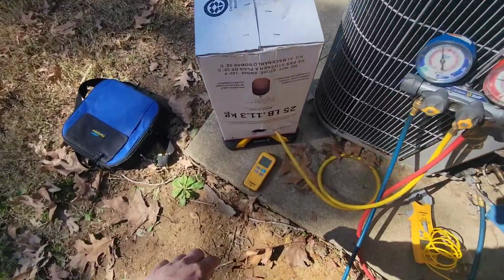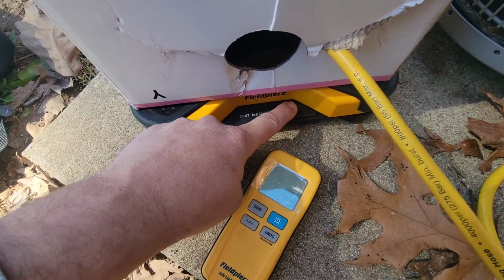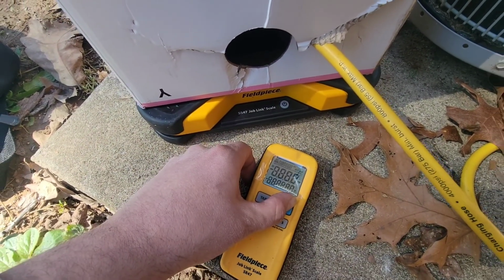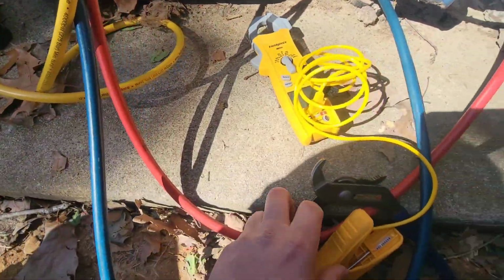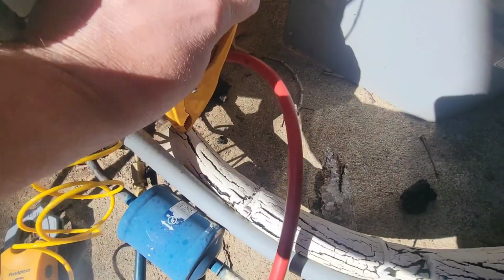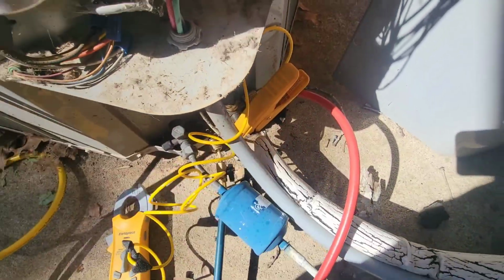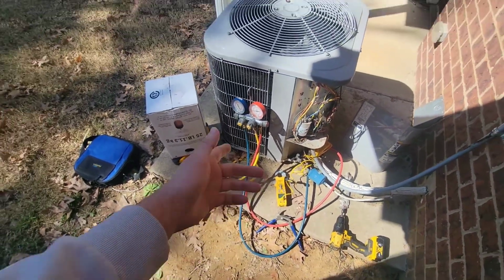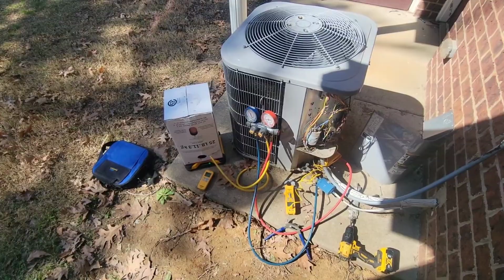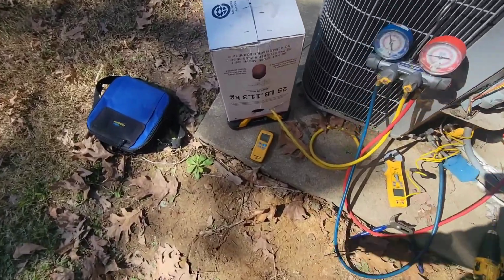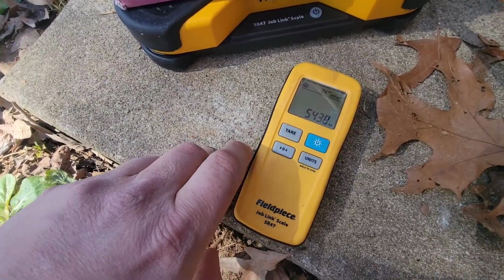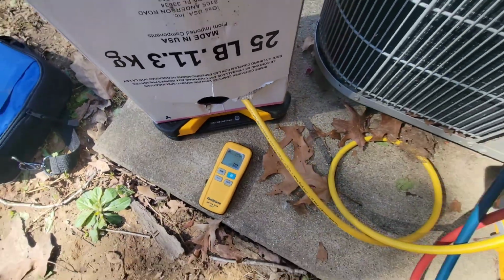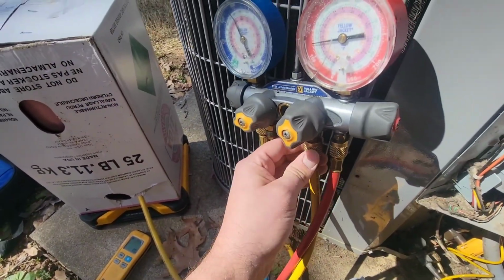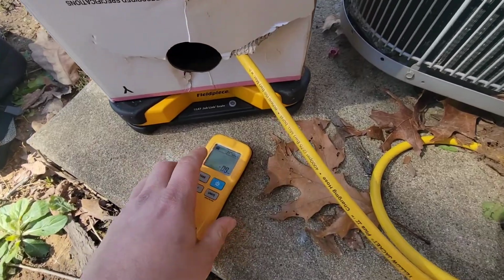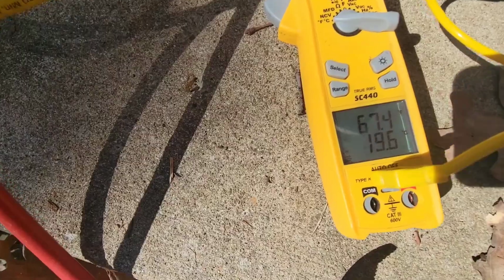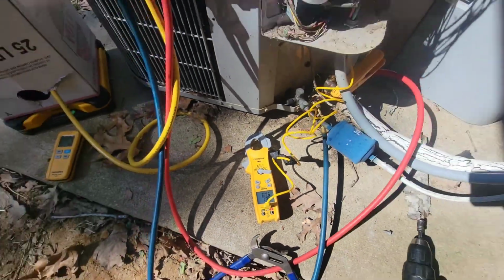Got my scales. Need to go ahead and turn my scales on. So of course we are going to charge this system, and what I'm going to do is I'm going to hook my pipe clamp right here on the vapor line because I want to measure that vapor temperature. It should be at least 100 degrees. It should be a lot more than that. You're going to see that as we charge the equipment. Scales are on. Now I'm going to zero it out. Make sure I bleed it. Okay. Zero it out again if you need. Okay. Meter is on. Now I'm ready to measure the temperature.